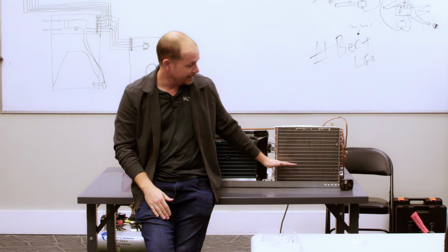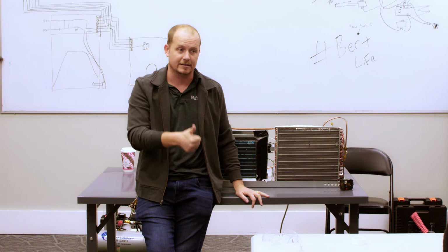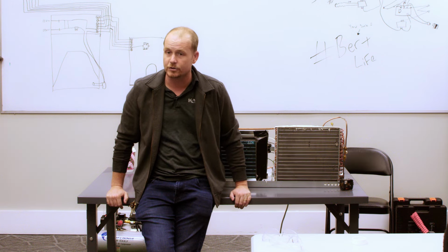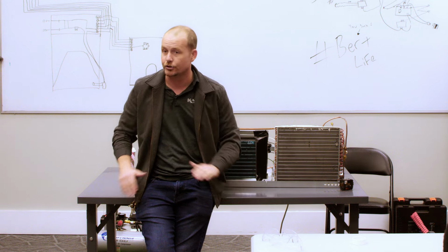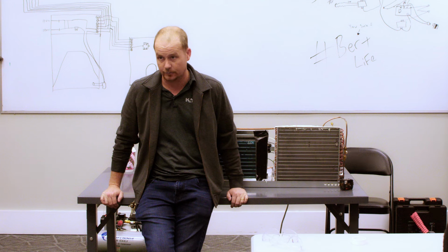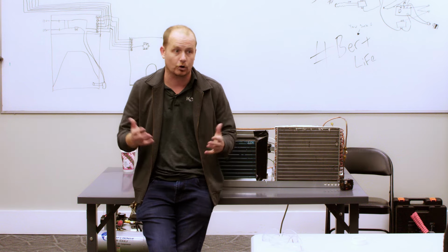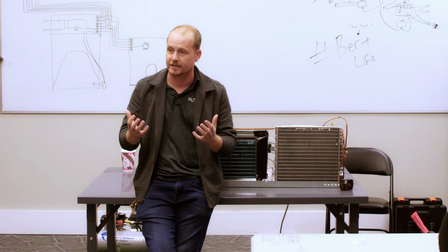But getting more subcool by driving up our condensing temperature, does that do us any good? No. And the point being, once our liquid temperature approaches the outdoor temperature, there's no sense in adding more. Any more you add, regardless of what your subcool number is at that point, is only going to drive up your head pressure and your condensing temperature, which increases your compression ratio. We've talked about it, makes your compressor work harder and in turn doesn't move as much refrigerant. So you reduce the efficiency when you do that.